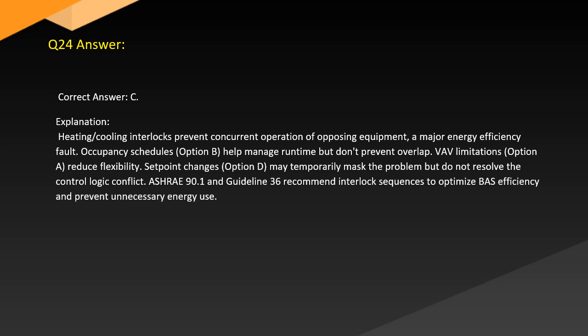Answer. Correct answer: C. Explanation. Heating-cooling interlocks prevent concurrent operation of opposing equipment, a major energy efficiency pitfall. Occupancy schedules, option B, help manage runtime but don't prevent overlap. VAV limitations, option A, reduce flexibility. Set point changes, option D, may temporarily mask the problem but do not resolve the control logic conflict. ASHRAE 90.1 and Guideline 36 recommend interlock sequences to optimize BAS efficiency and prevent unnecessary energy use.